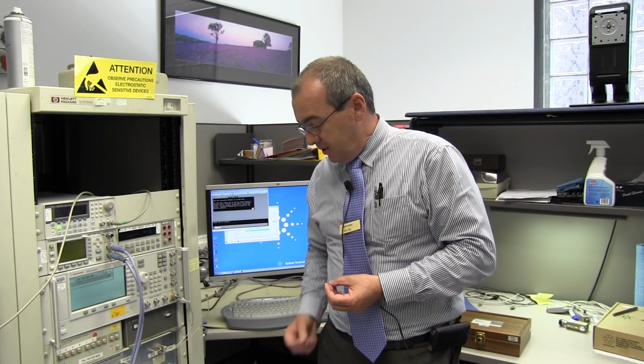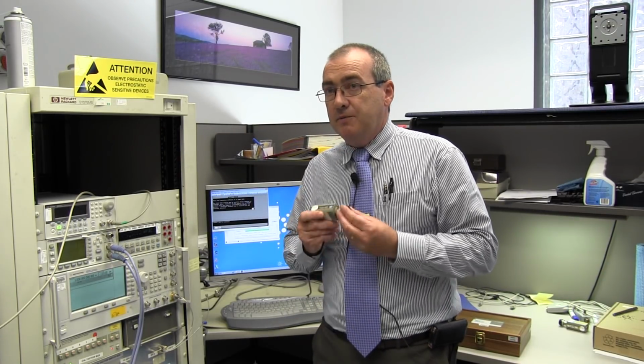Every time we do a new sensor for a customer, we're doing a validation on our reference sensor against our validation sensor. Not just for the power, but also for the VSWR of the sensor. VSWR is a significant component. If you use the simple method, you're not actually taking into account the uncertainty associated with the VSWR of your device under test.